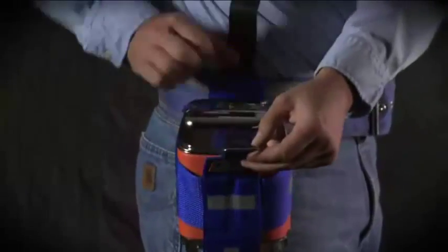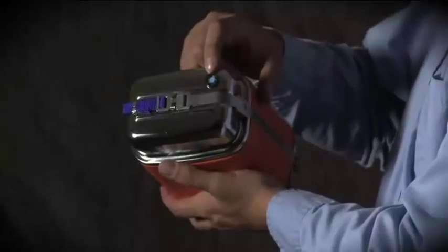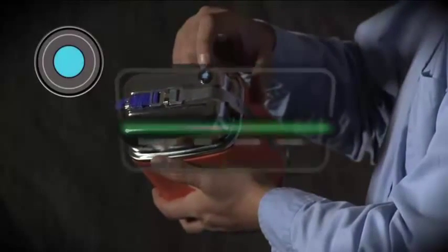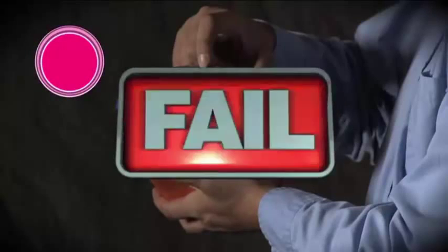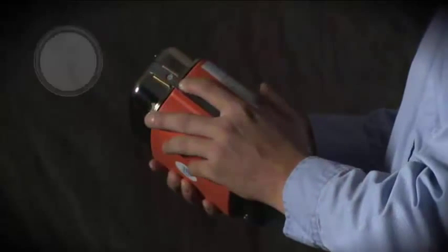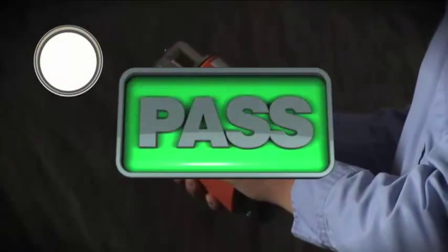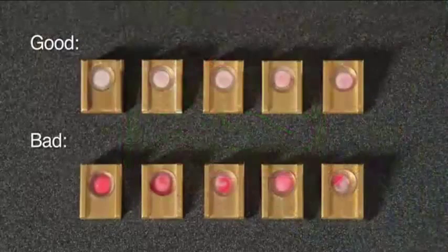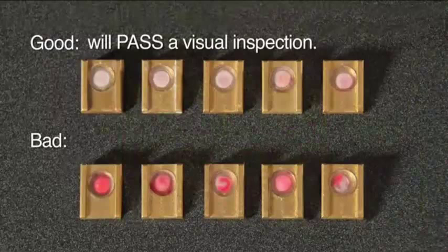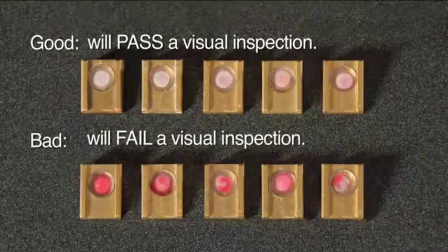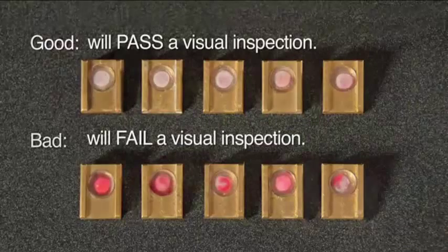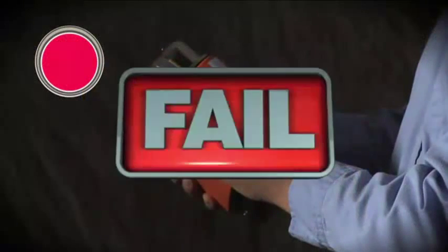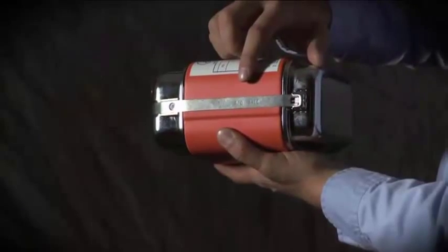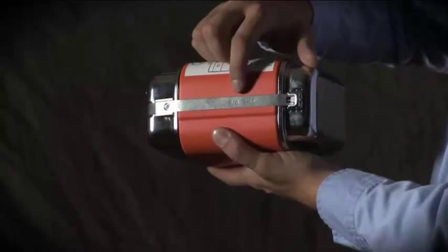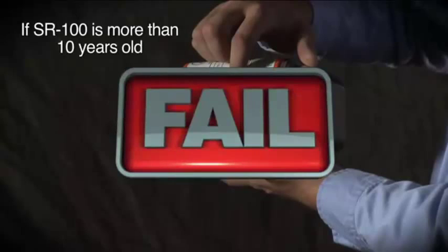Here's what to look for if you carry the orange model SR100. The top and bottom moisture indicators should be solid blue. If either one is white or pink, take it out of service. The temperature indicator should be white. It may show a faint dark or pink shadow, circle, or pattern. Examine these indicators shown here. The top row represents good indicators that would pass a visual inspection. The bottom row represents bad indicators and would fail a visual inspection. If the temperature indicator is red, take it out of service. Now, check the date of manufacture. It's marked on the stainless steel security band. If it's more than 10 years old, take it out of service.